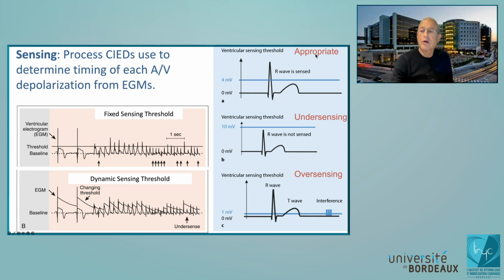Here we can see that the R wave is sensed correctly or appropriately, as that's the jargon we use. Here, if we set the sensing threshold higher, at a greater value than the R wave amplitude, we don't sense the R wave. We refer to this as undersensing. This is a sensing threshold that's set too high. Here, you can see that the sensing threshold will sense the R wave when it's set at a millivolt, but it will also sense the T wave and other potentially small signals. So here, when we sense signals that are undesired, we call this oversensing.